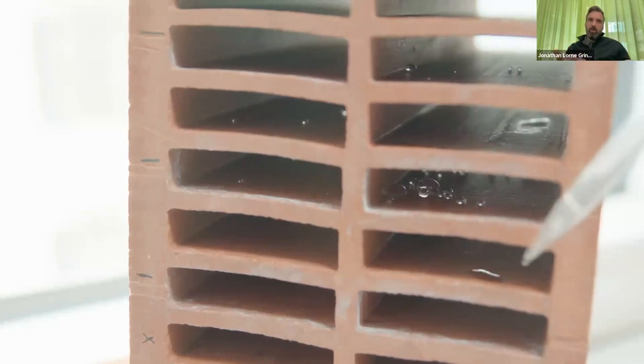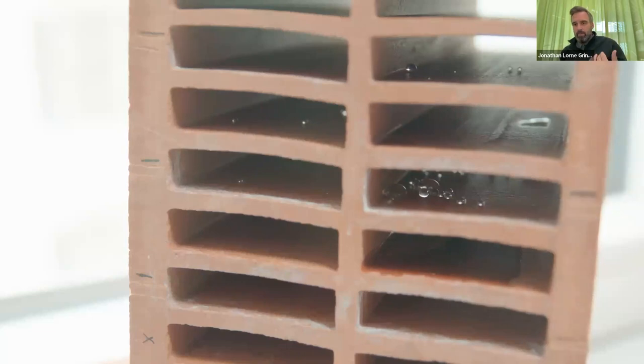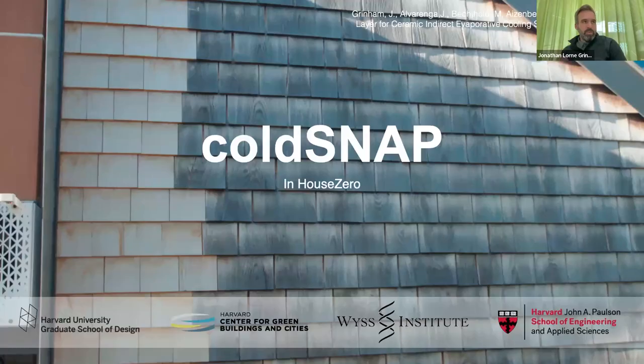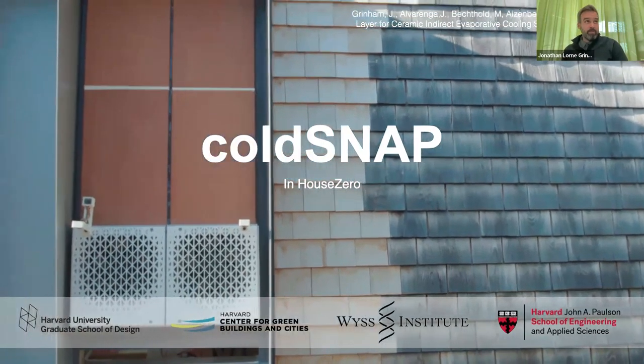That cooling will conduct over to the dry channel and cool the air that enters the building, but without having that moisture transfer. So we're getting cool, dry air in the sense of however dry it was when it came in, and we're getting a big bump in our cooling capacity. So with that in mind, we took this unit and we installed it in House Zero, which I shared before.